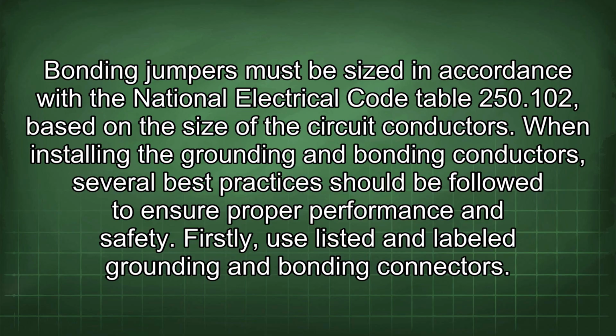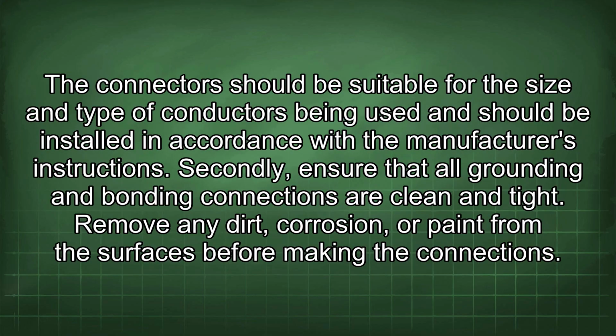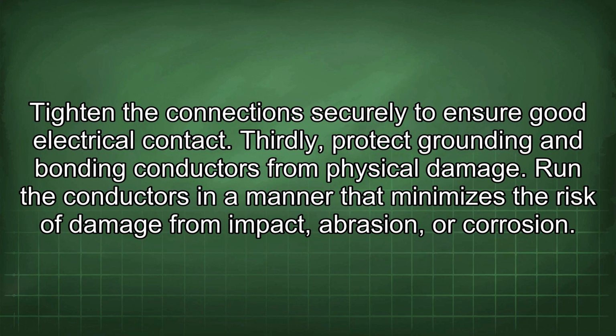When installing the grounding and bonding conductors, several best practices should be followed to ensure proper performance and safety. Firstly, use listed and labeled grounding and bonding connectors. The connectors should be suitable for the size and type of conductors being used and should be installed in accordance with the manufacturer's instructions. Secondly, ensure that all grounding and bonding connections are clean and tight. Remove any dirt, corrosion, or paint from the surfaces before making the connections. Tighten the connections securely to ensure good electrical contact.